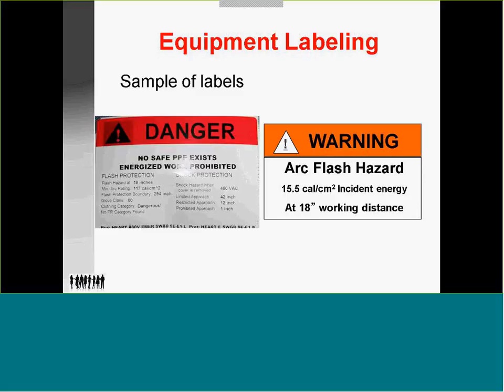Here, the label on the left is marked with danger. No PPE exists. This is with 117 calories, which means no way you can be protected. Over here is a warning. We're at 15.5 calories, which is a category 3, which we'll be discussing shortly. 18 inches working distance from that. These labels are supposed to be on all panels where it can be opened and where a termination exists. Not a junction box, but a termination panel.